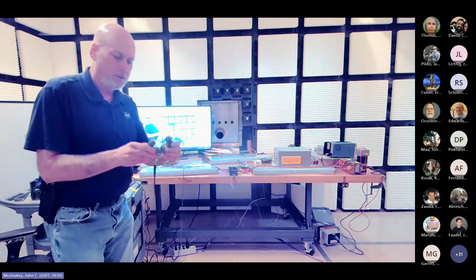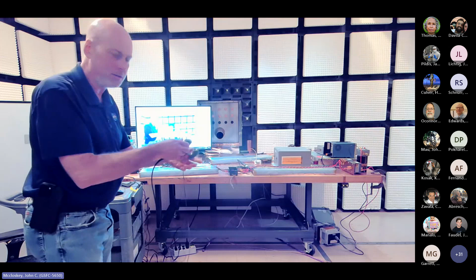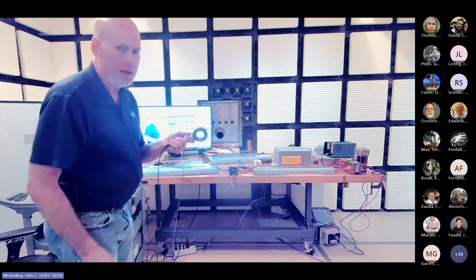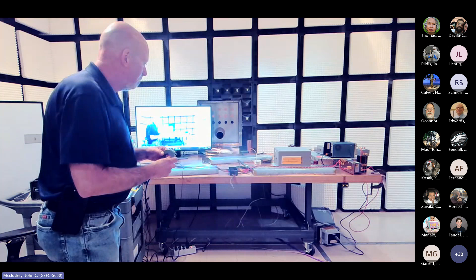And when you're done, you unclamp it, remove it, no problem, as long as you've got room to get it. If it's a group of cables all tied together with tie wraps, well, maybe you need to clip a few tie wraps. But if you're trying to troubleshoot a problem, clipping a few tie wraps to get a current probe in there to see which is your culprit cable may be a worthwhile thing to do. But just for doing this testing, even on the bench, or when you bring it in here for a full up EMI test, this is one of the most efficient and I think one of the most valuable tests we can do. It's very easy to do.